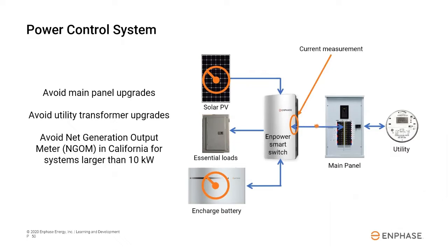And then second is a requirement that's specific to California utilities. So if you're not in California, you can ignore this next part. You can avoid installing what's called a net generation output meter, or NGOM, which is normally required for battery storage systems that are over 10 kilowatts in power capacity. So that can be a huge money saver. Usually it's around $2,000 to $2,500 in total cost when you factor in the hardware, labor, and administrative costs of the NGOM.